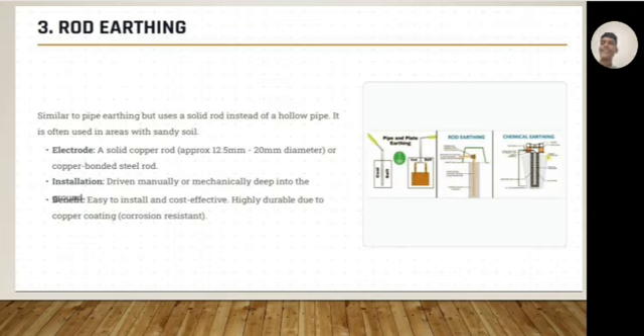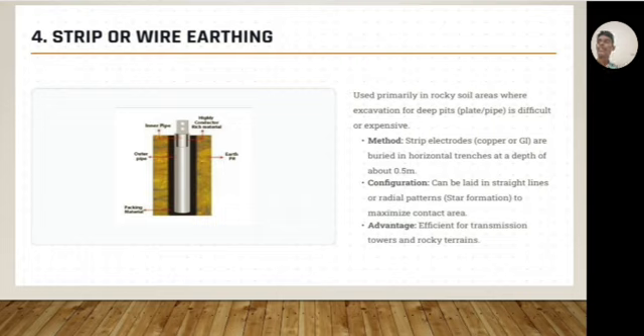This is the diagram of rod earthing. Fourth, strip or wire earthing, used primarily in rocky soil areas where excavation for deep pits is difficult or expensive. First point, method. Strip electrodes are buried in horizontal trenches at a depth of about 0.5 meters. Configuration can be laid in straight lines or radial patterns.